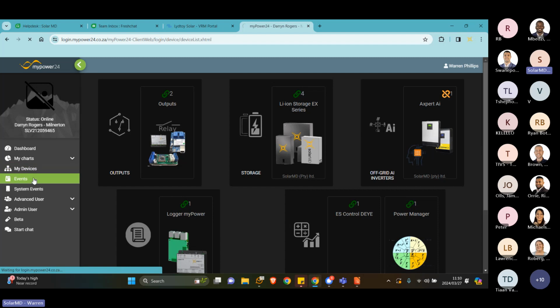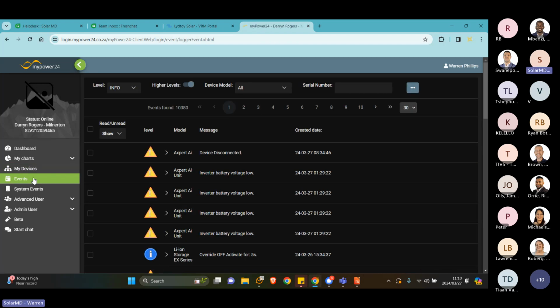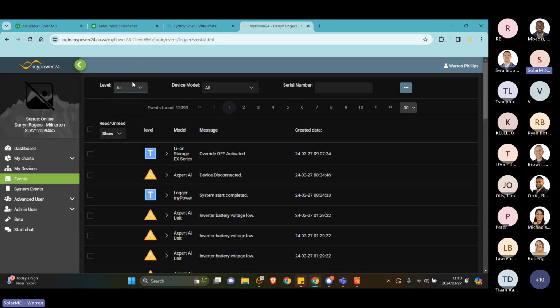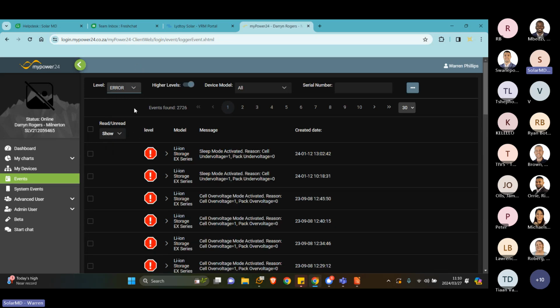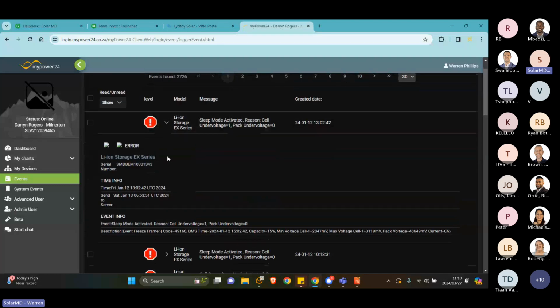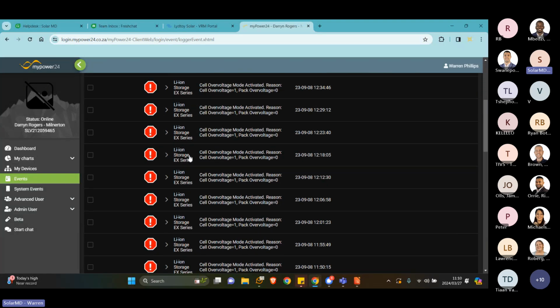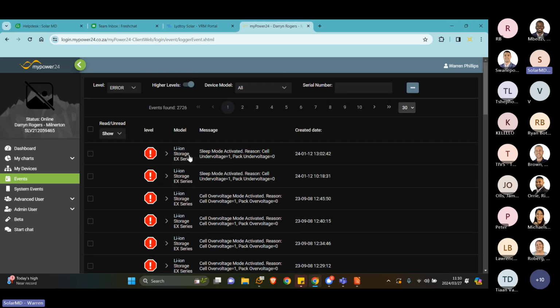Okay, so if you're trying to troubleshoot problems, looking at the events tab can often give you a brief overview of what the problem is. And so we can see here, it's all time stamped. You can see on this particular year, on this day and month, at that time, one of the batteries was discharged too far. If it's one of our modern BMSs, it'll tell you all the parameters. Those are all captured at that point in time when that event occurs. It'll tell you that the capacity was 15% remaining, what the minimum and maximum cell voltages were at the time, and so on.